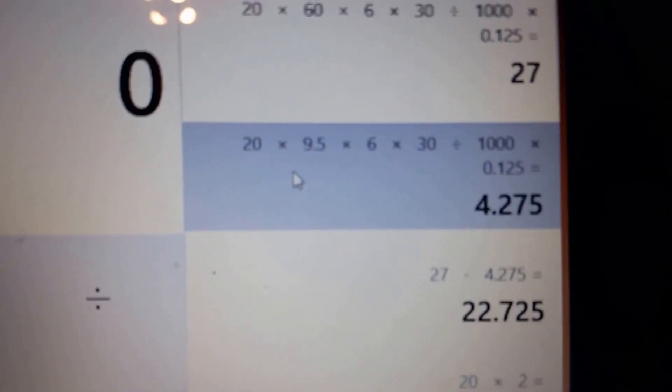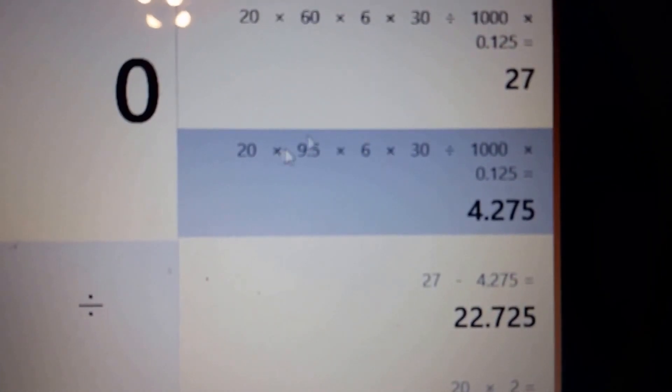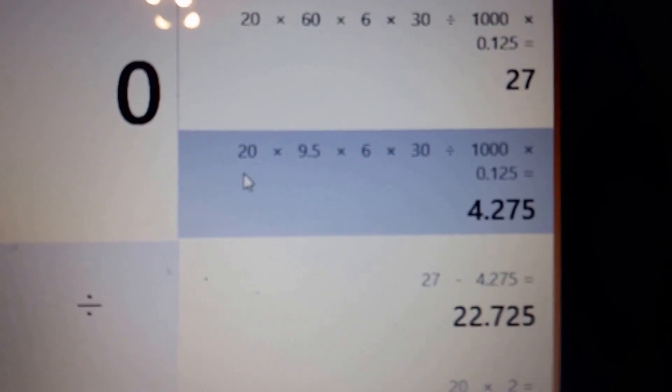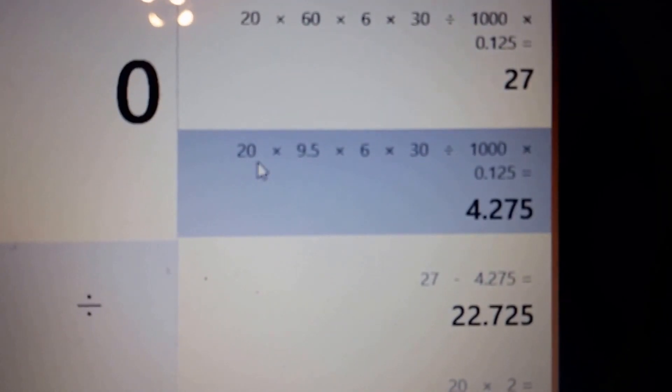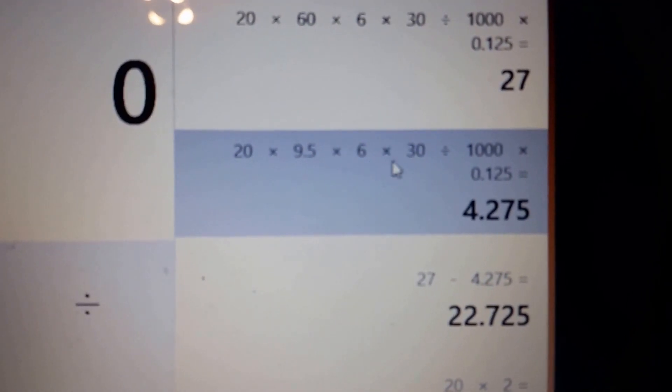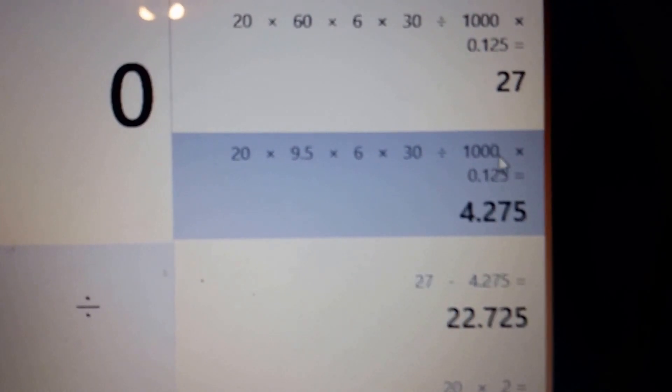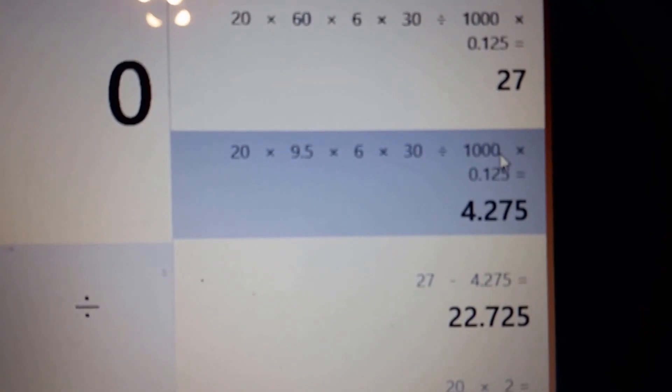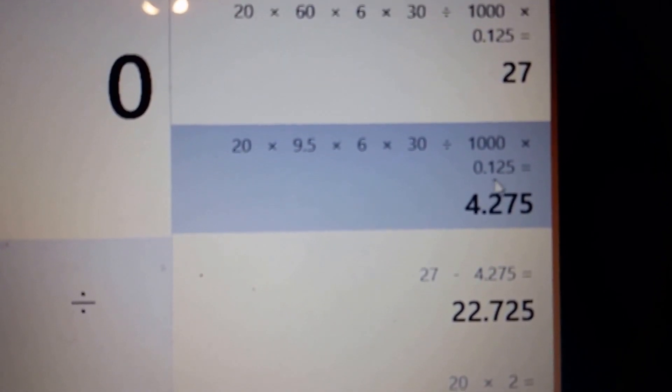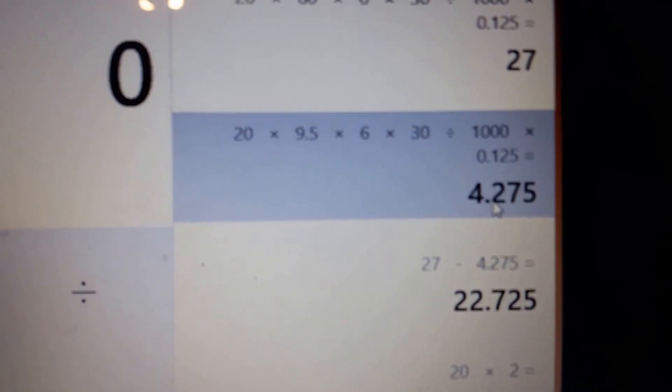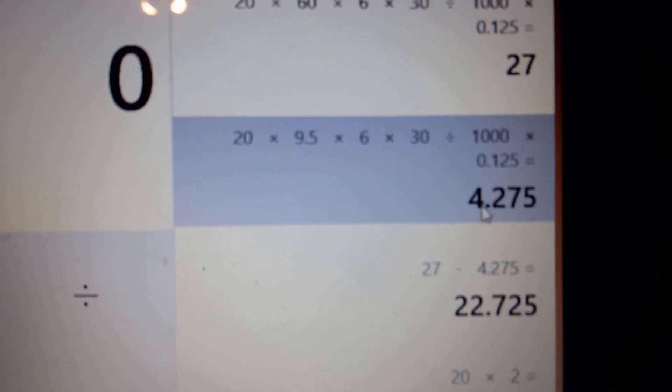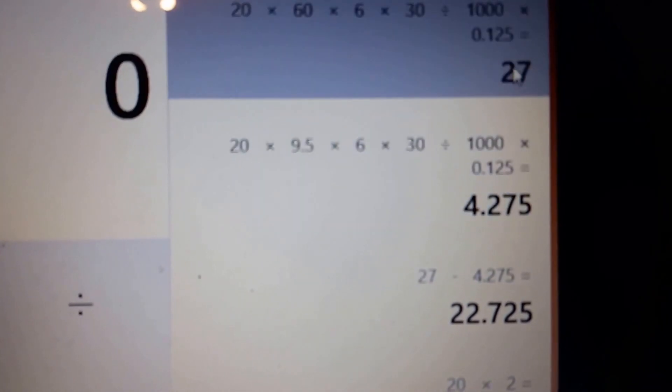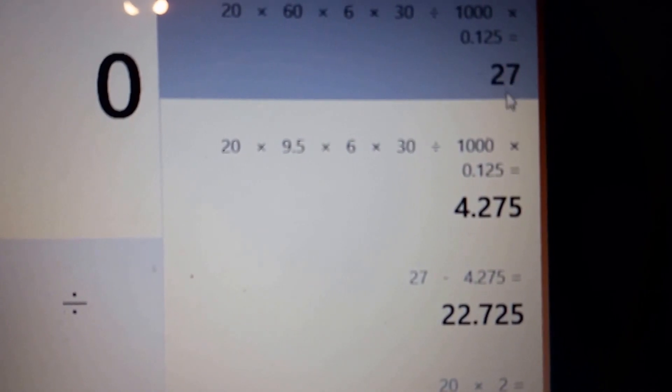But when we switch over to the LED, that was the incandescent. So this is the LED. Now you run 20 bulbs at nine and a half watts, six hours a day, times 30 days, divide that by 1000 to get into kilowatts times 0.125 kilowatt hours. So the LEDs cost $4.27 to run. The incandescent costs $27.